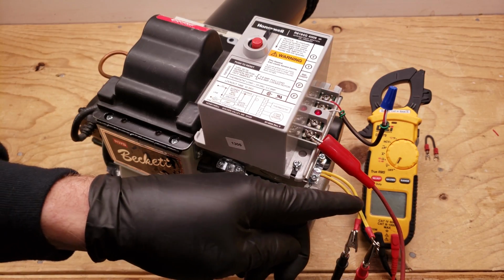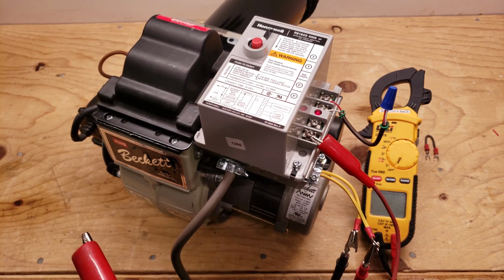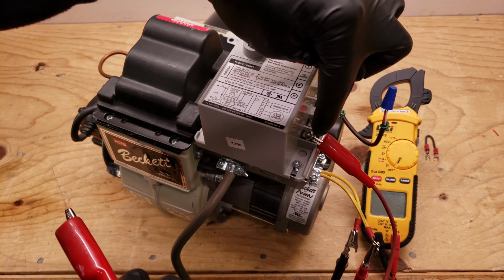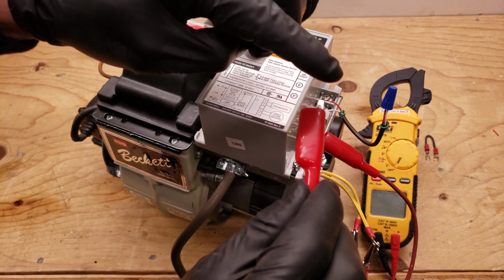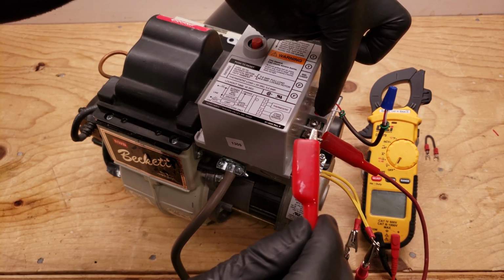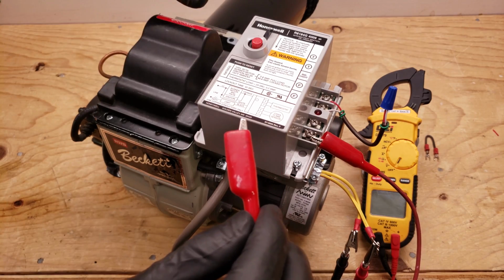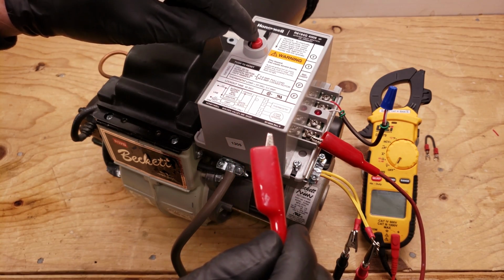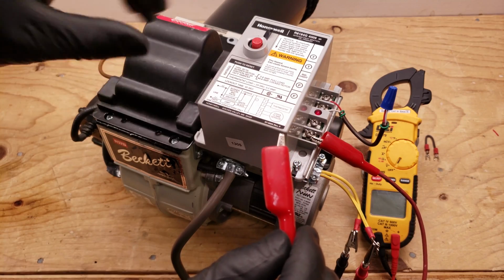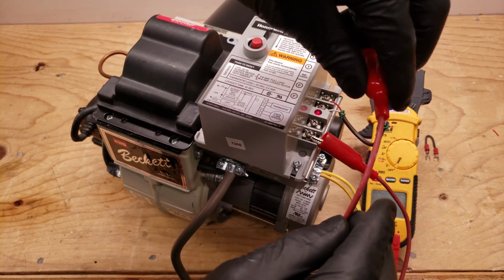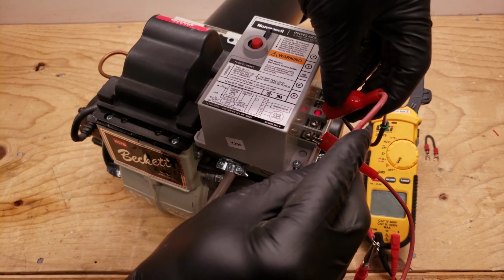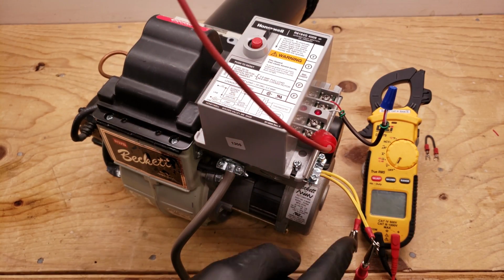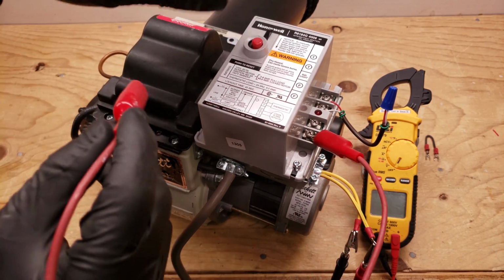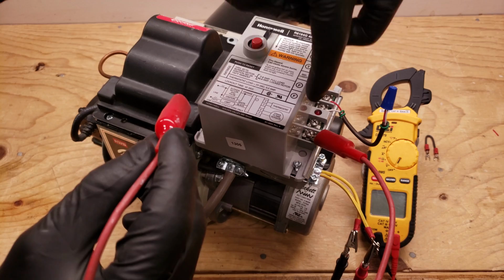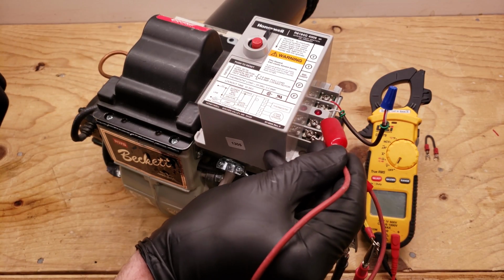Now, if you want to read your resistance on the CAD cell while the burner is in full operation, then what you could do is put an alligator clip on the one F terminal, and get ready to put the other one on the second F terminal after the burner turns on. So if I press this red button as the reset, I can then have this burner start up and then go ahead and place this other alligator clip on this terminal, and then I can just go ahead and read my resistance value on the CAD cell, and this should not shut off on me. And that's because we have a low resistance value across the F and the F terminals if we have it jumped out with alligator clips.